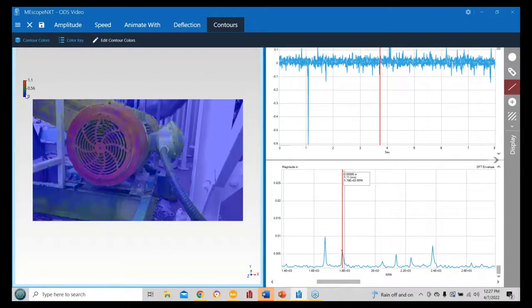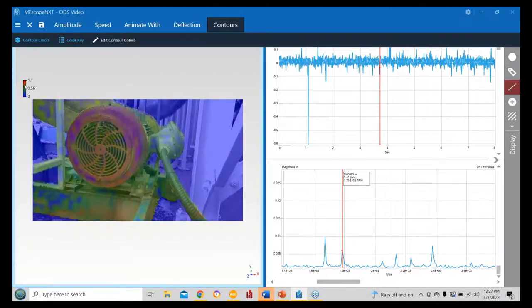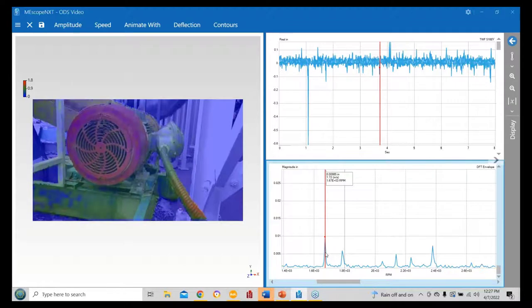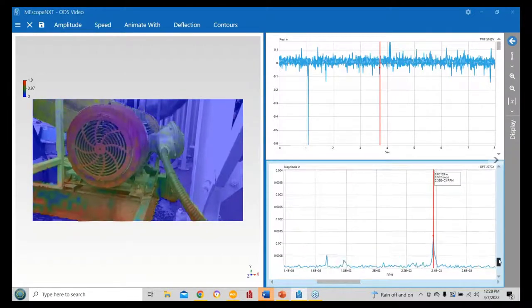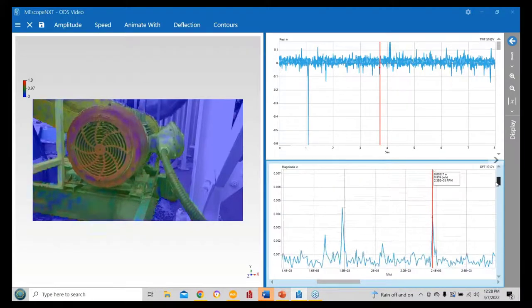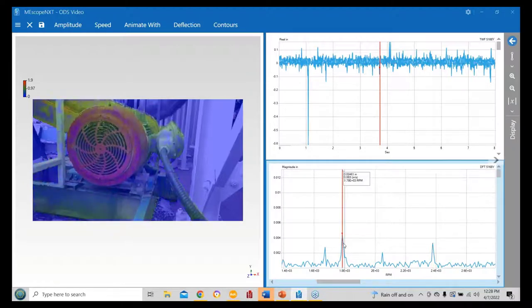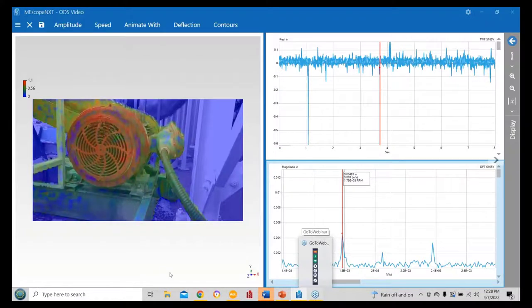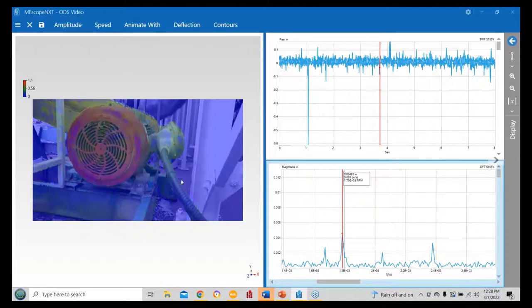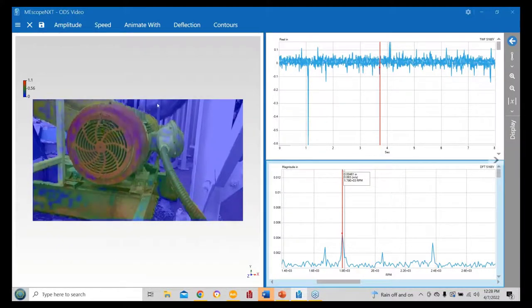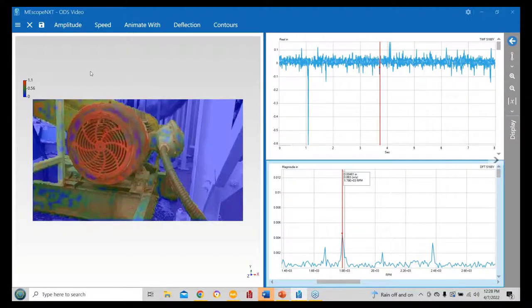With color contours on, vibration on this machine was around 0.6–0.7 inches per second — really high. I can see the entire frame bouncing, the motor going with it, and the belt drive shield bouncing up and down. The motor shaft is at maybe 0.7 inches per second — much higher than we want. In the software you can go from peak to peak and see the different shapes. There's a little twist in the motor, some bouncing, and thrusting in and out toward us.